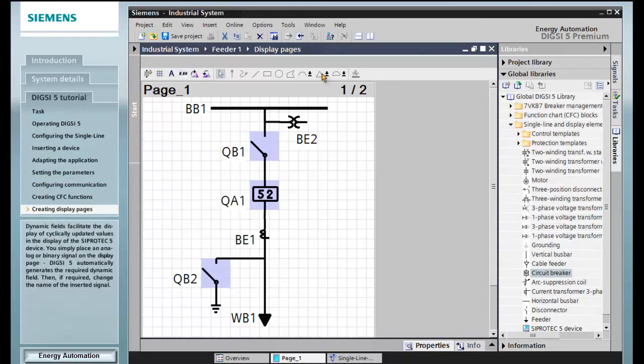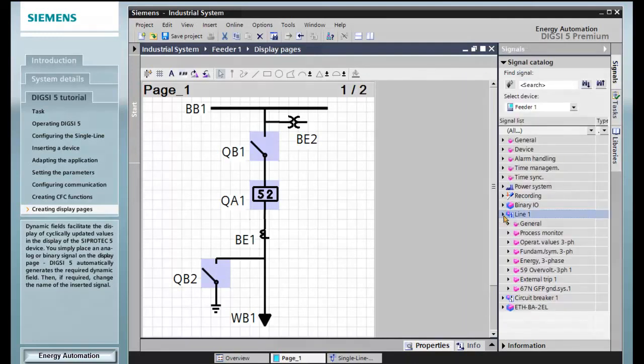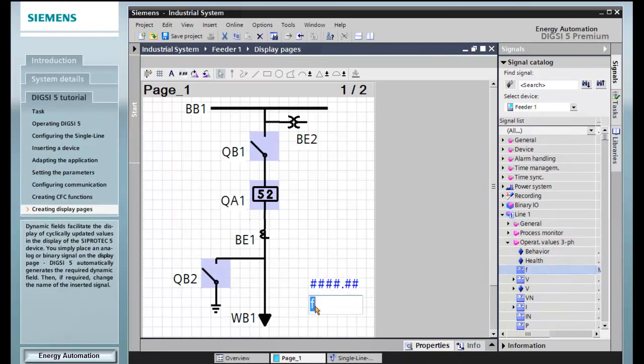Dynamic fields facilitate the display of cyclically updated values in the display of the Siprotec 5 device. You simply place an analog or binary signal on the display page. DIGSI 5 automatically generates the required dynamic field. Then, if required, change the name of the inserted signal.